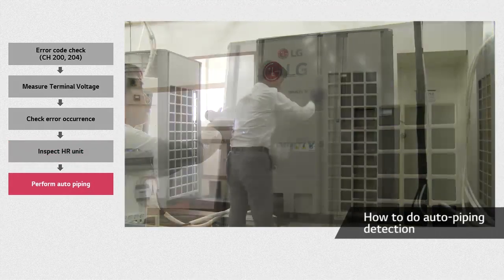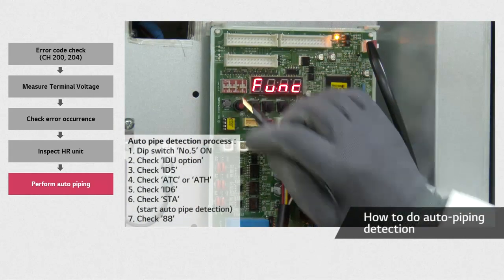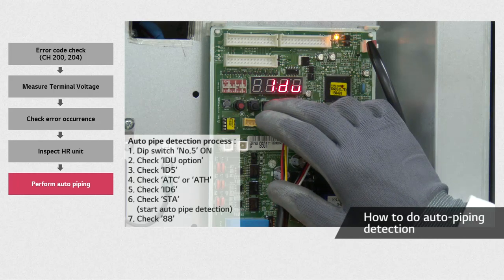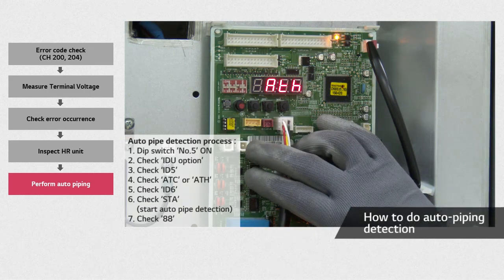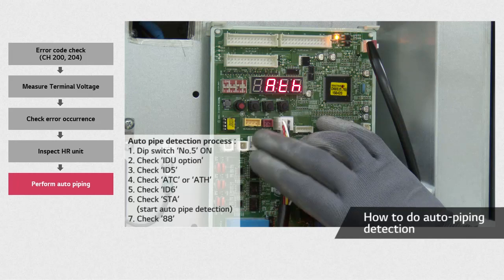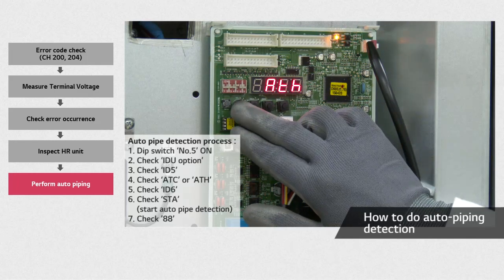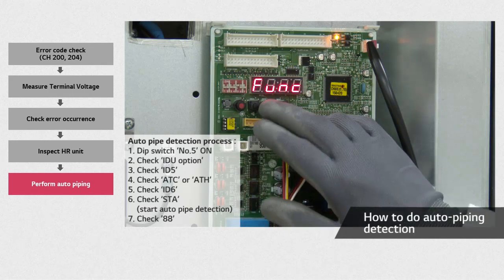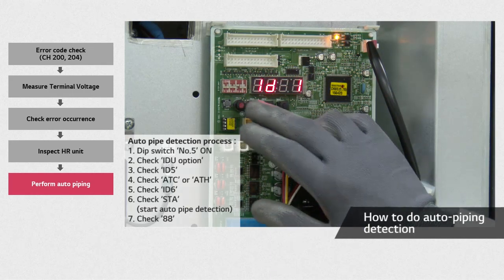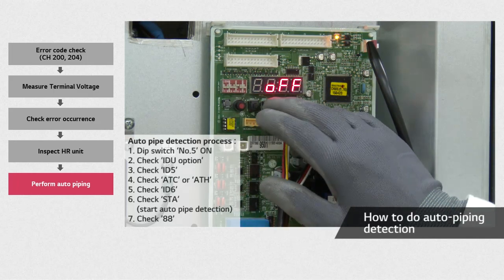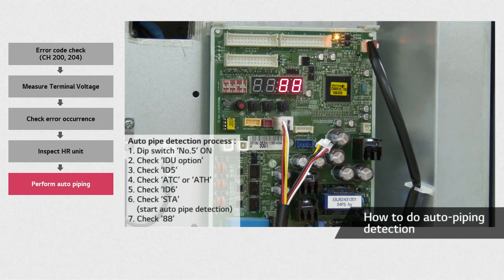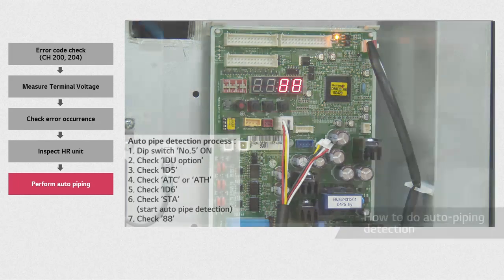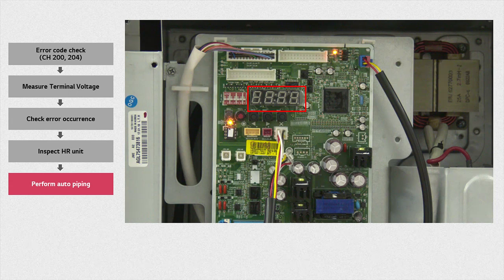Now, remove the front panel on the outdoor unit. After adjusting the HR unit DIP switch according to the IDU number, you will need to perform auto-pipe detection. To do this, turn on the DIP switch and after selecting the indoor unit number, select ID5. If the ambient temperature is below 15 degrees, ATH will show up. Finally, after setting ID6 and waiting for a while, 88 will show up on the screen and the piping detection will begin. After the DIP switch is properly set and the pipe detection appropriately done, error CH200 will disappear.